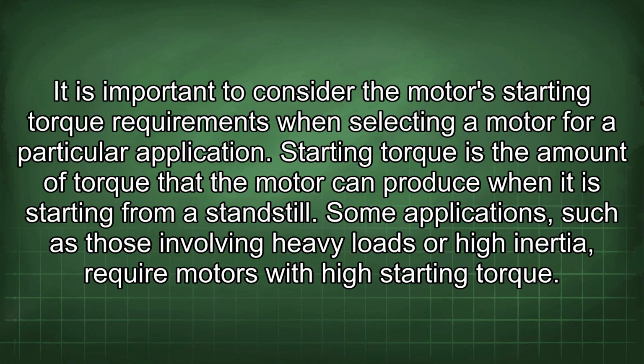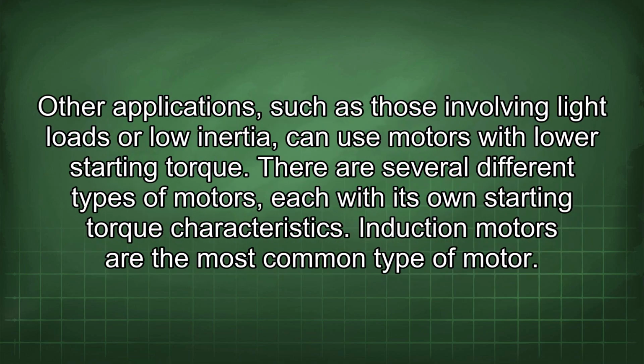It is important to consider the motor's starting torque requirements when selecting a motor for a particular application. Starting torque is the amount of torque that the motor can produce when it is starting from a standstill. Some applications, such as those involving heavy loads or high inertia, require motors with high starting torque. Other applications, such as those involving light loads or low inertia, can use motors with lower starting torque.